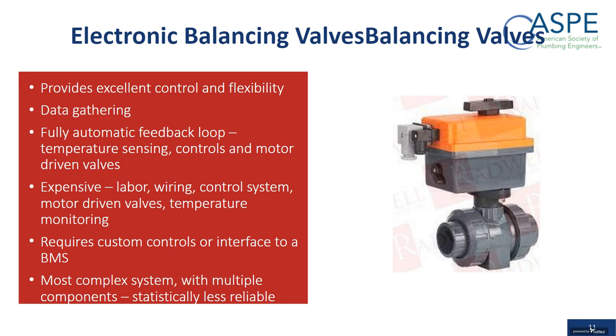They're fully automatic, so basically they consist of some type of temperature sensing device, controls, and the valves are motor driven. They tend to be more expensive than all the other types of balancing valves because there's a lot of labor associated with these. You have to run wires for the motors and for the temperature sensing. So that can take a lot of labor. And then you need some type of a custom controller, like a building management system or something else, to interface to these valves.